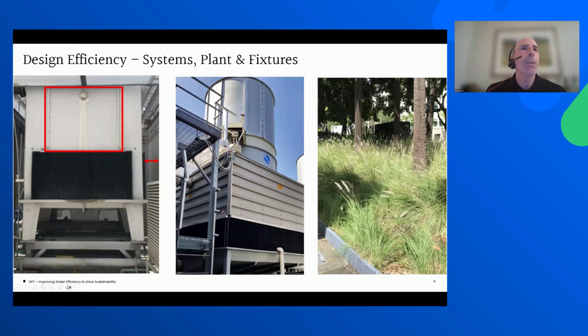Over here on the left, in this first image, you can see I've highlighted what's called an inspection panel, and all cooling towers typically have one large removable inspection panel. This particular one's quite a fair way off the ground, and it will be very difficult to get to what's behind there, which is a lot of the fill pack and also the water distribution network. That's really important because cooling towers must have a good supply of air through the tower, as well as discharge at the top. The other design point I've highlighted, you can see this little arrow between, shows how close this cooling tower is against the side of the wall, and there's a wall behind it that's also very, very close, and that's reducing the amount of airflow coming into the tower.